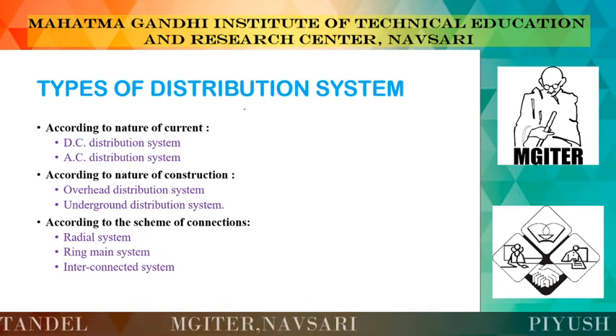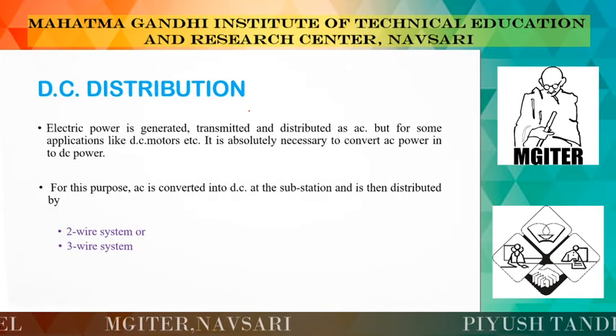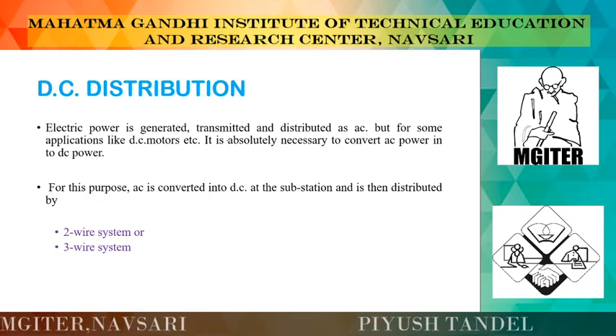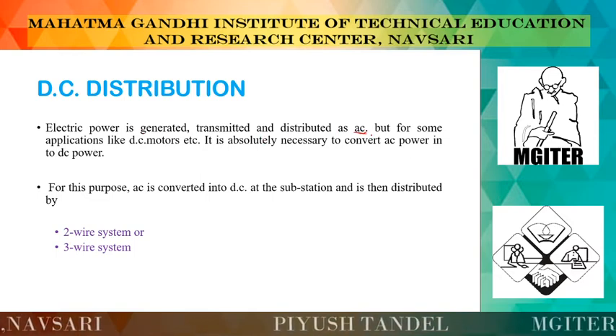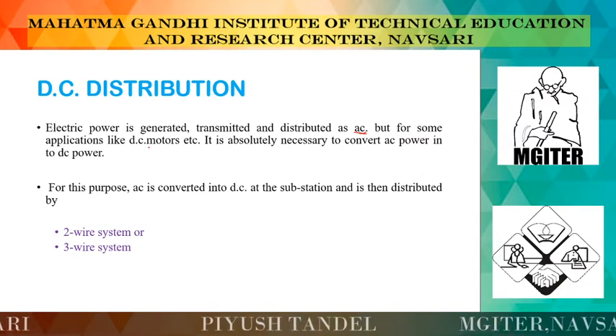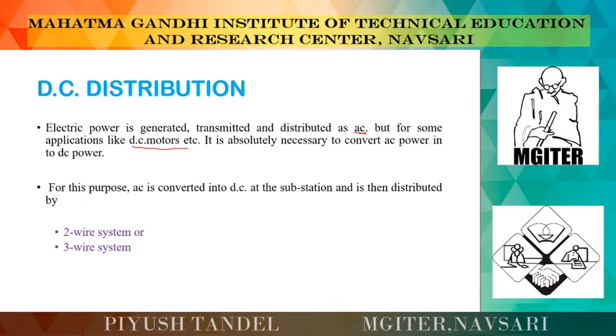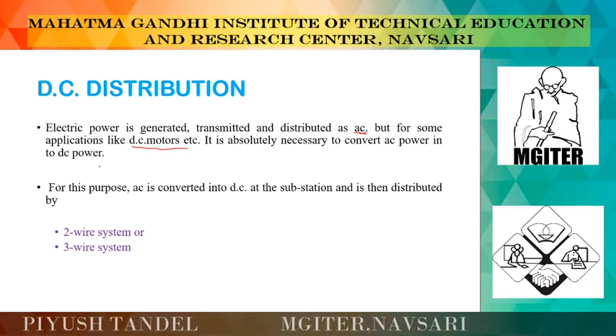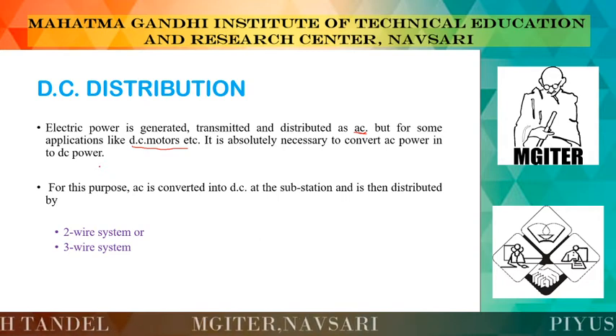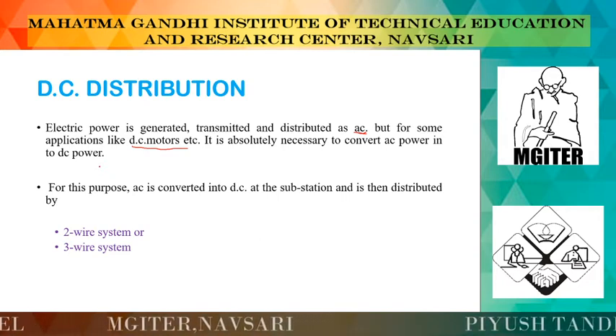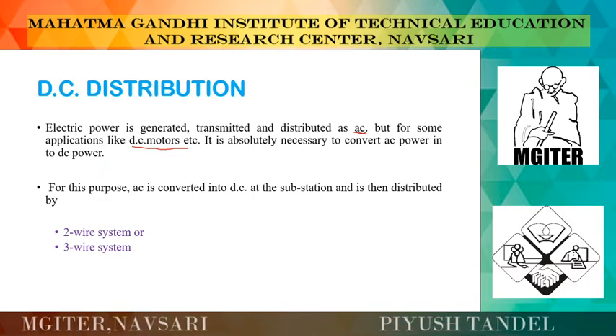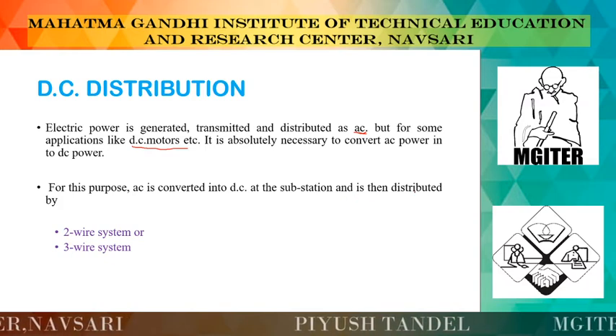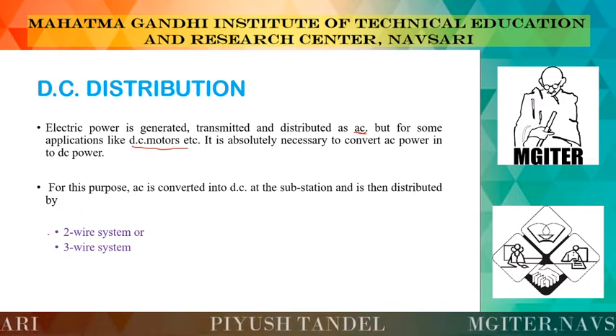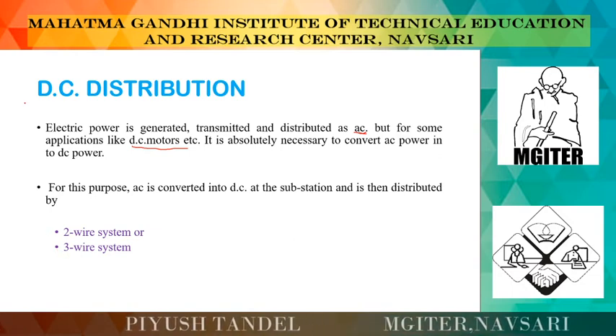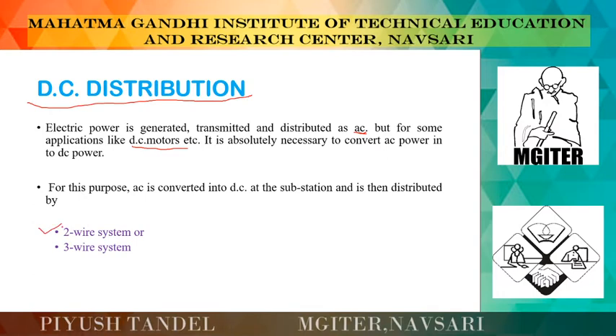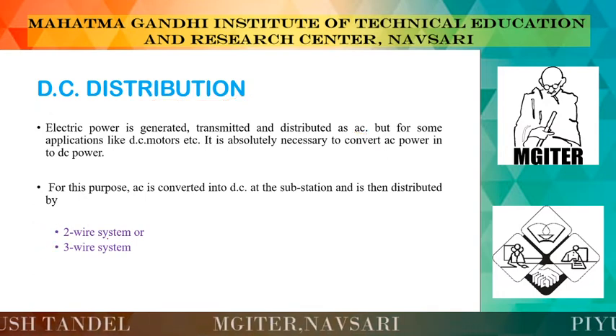So if we talk about the first one, according to the nature of current, we can talk about the DC distribution system. Electrical power is generated, transmitted and distributed normally as AC. But for some applications like DC motors, it is absolutely necessary to convert AC power into DC. We have several applications of DC, like the traction system, because in the traction system we are using a DC series motor, right? So for that we need to convert the AC power into DC power. For this purpose, AC is converted into DC at a substation and it is distributed by two methods: the two wire system and the three wire system. So in the DC distribution system, we have these two types, the two wire system and the three wire system. Now what is the two wire system?